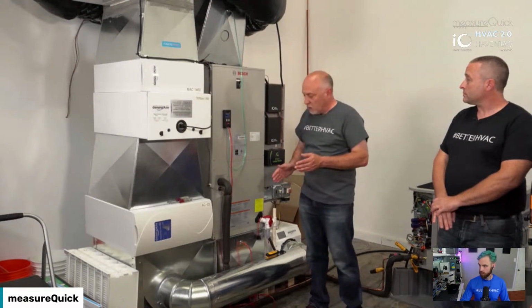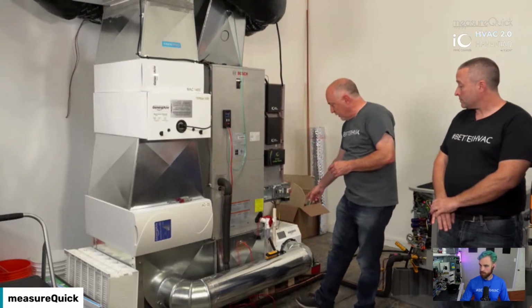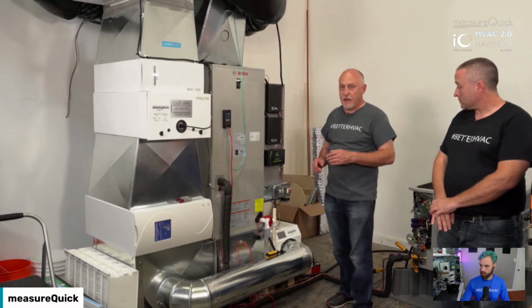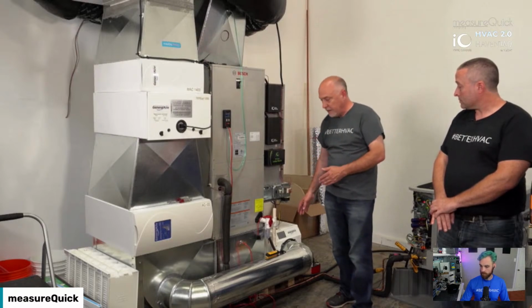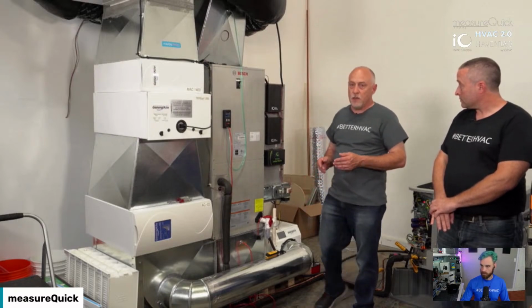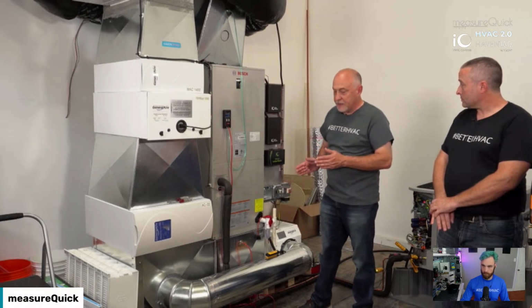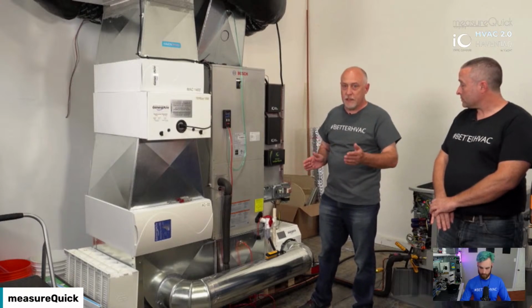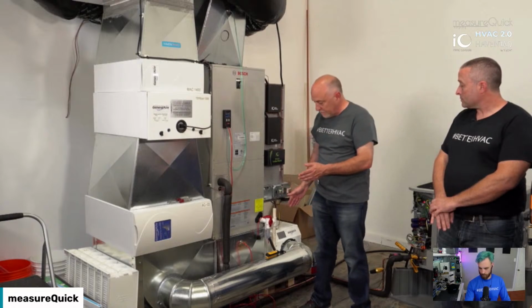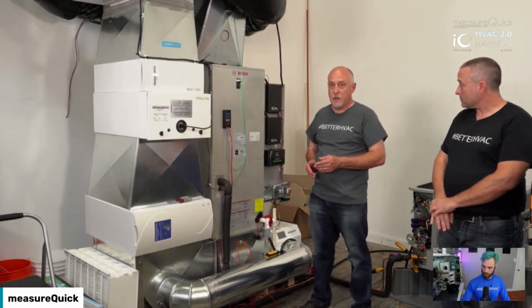We've also got tied into this a General Air DH75, which is a dehumidifier. So what we're doing on the dehumidifier is pulling out the latent load. We're finding that, interestingly enough, even though the system is really sized well for the shoulders, it's a bit of a challenge to control the latent load in here all the time.